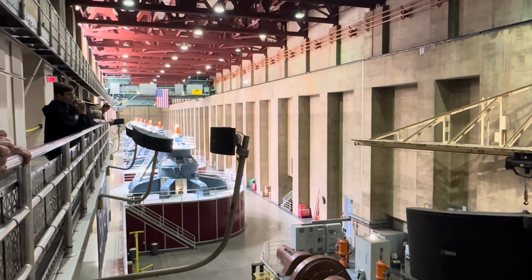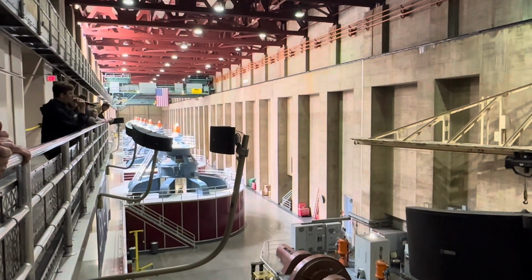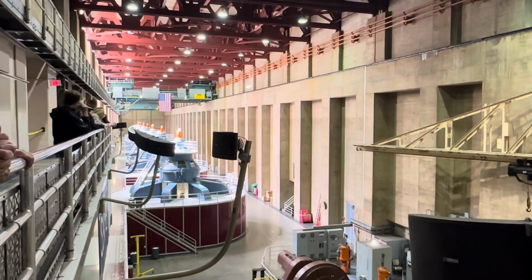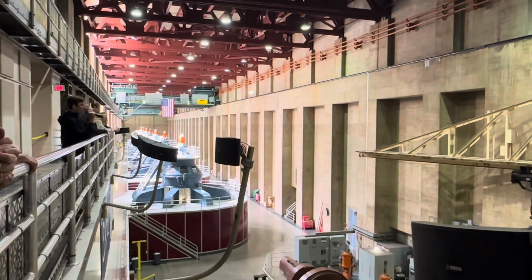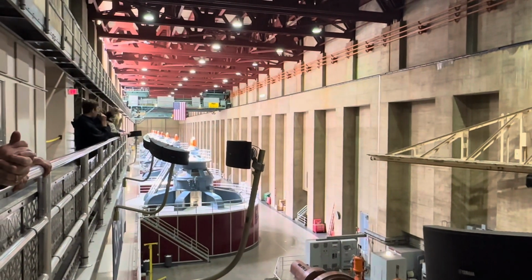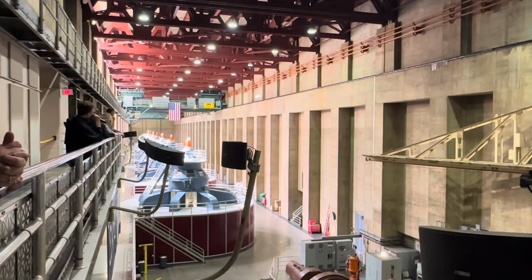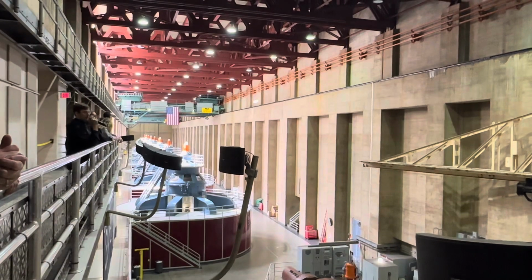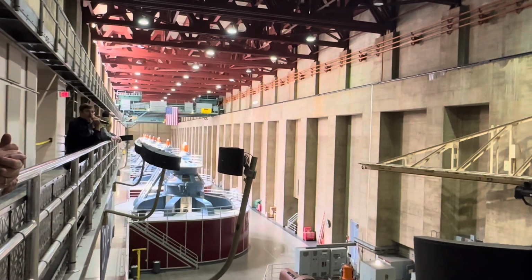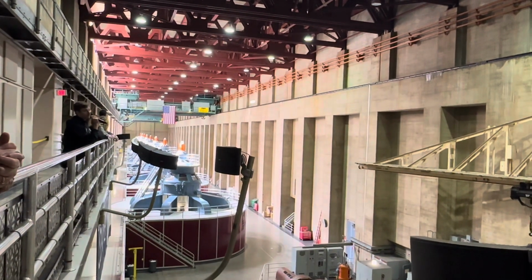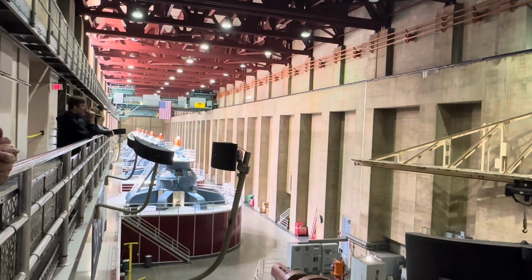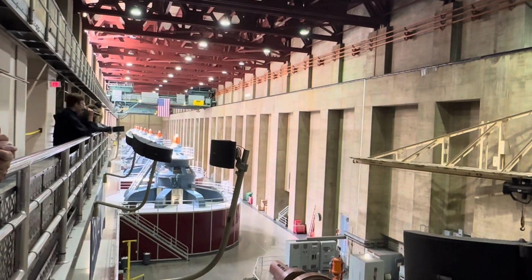Now, in order to maintain these generators throughout the years, and they are all original from whenever they were installed, we have the green bridge cranes that you see at the top of the wing. Those cranes can move along the tracks you see on the sides here, and those cranes then can be combined together over a particular generator. When they are combined, they have the necessary 600-ton lifting capacity that we need to lift up the rotors inside those generators and perform maintenance on those.